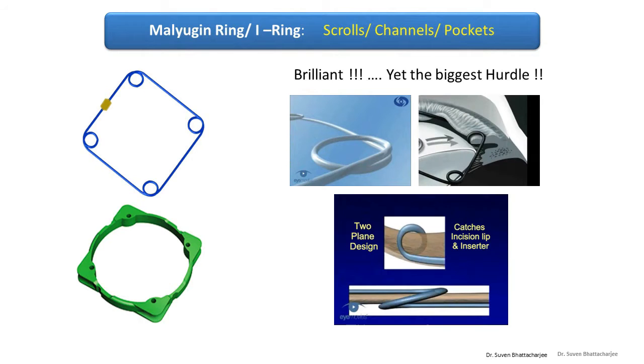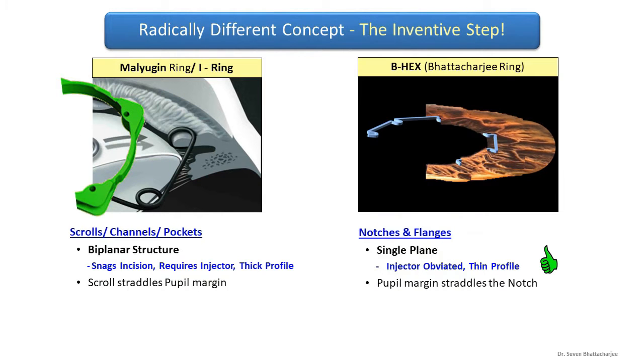The need for a better pupil expander stemmed from the fact that the scrolls of the Malyugin ring, though brilliant, are biplanar and are responsible for snagging the incision and crushing of the iris. The radically different, inventive step is the uniplanar design of the BHEX.